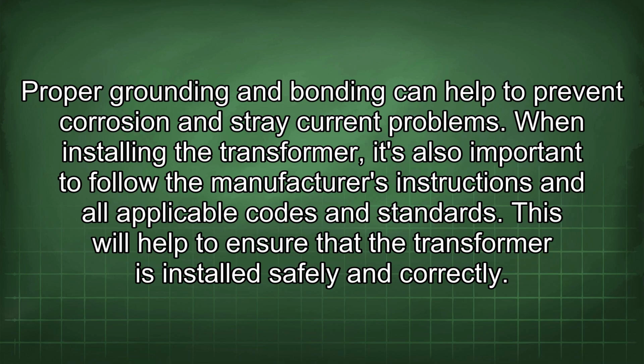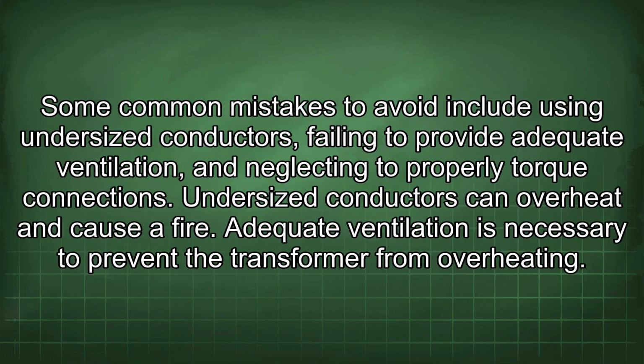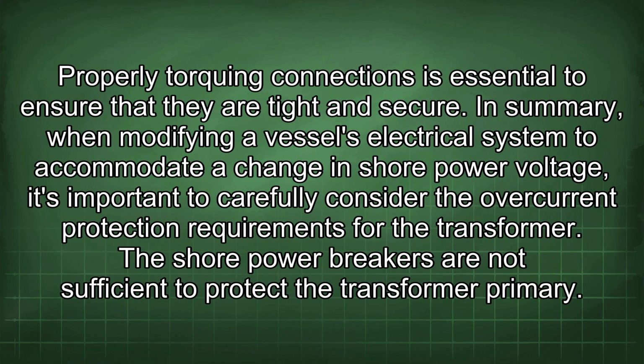When installing the transformer, it's also important to follow the manufacturer's instructions and all applicable codes and standards. This will help to ensure that the transformer is installed safely and correctly. Some common mistakes to avoid include using undersized conductors, failing to provide adequate ventilation, and neglecting to properly torque connections. Undersized conductors can overheat and cause a fire. Adequate ventilation is necessary to prevent the transformer from overheating. Properly torquing connections is essential to ensure that they're tight and secure.